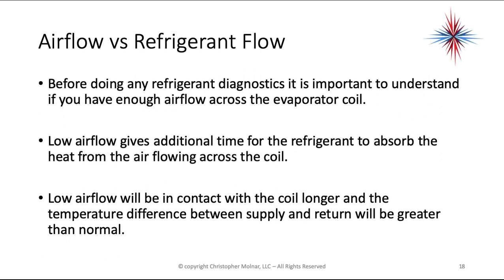Before doing any refrigerant diagnostics, it's important to understand if you have enough airflow across the evaporator coil. Low airflow gives additional time for refrigerant to absorb heat from the air passing across the coil. Low airflow will be in contact with the coil longer and the temperature difference between supply and return will be greater. The longer air — a substance with mass — sits on that evaporator coil, the more heat is pulled out of it, so the difference between supply and return air temperatures will be greater than normal.